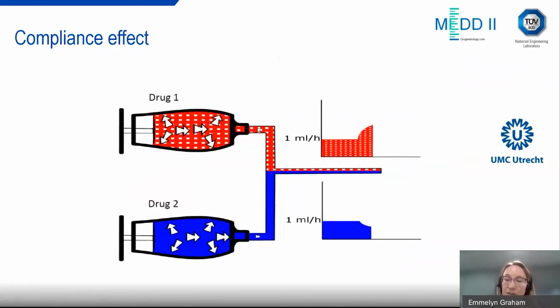However, this can also then have an effect on the other syringe, in that the increase in the pressure from increasing the flow rate in the red syringe will actually cause an expansion and compliance effect in the blue syringe. And because that's absorbing and expanding, what we're getting is a decrease in that flow rate, which is being delivered to the patient.